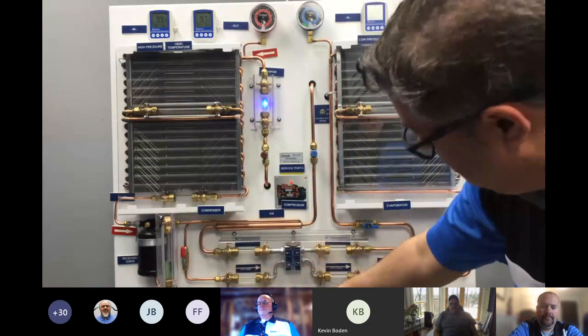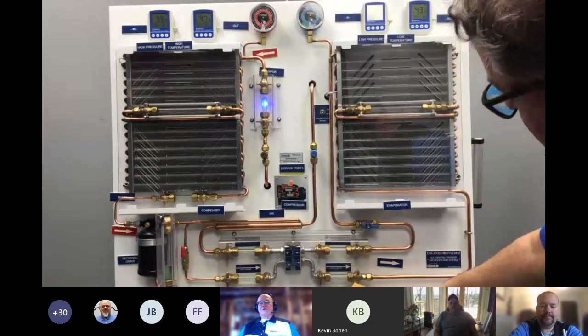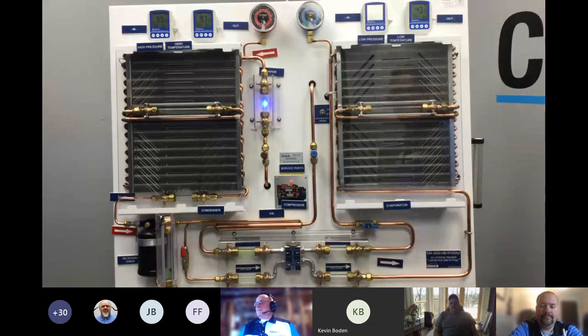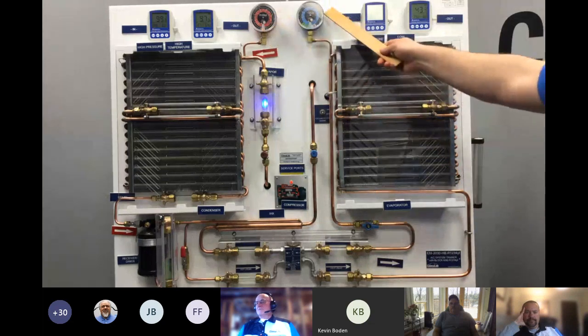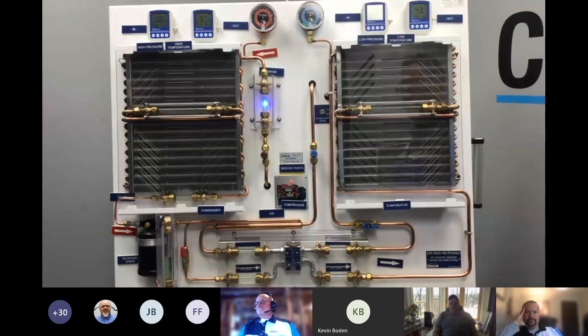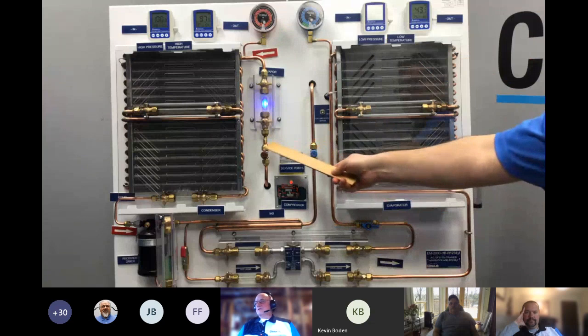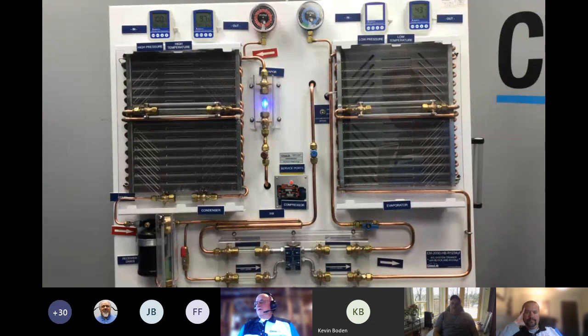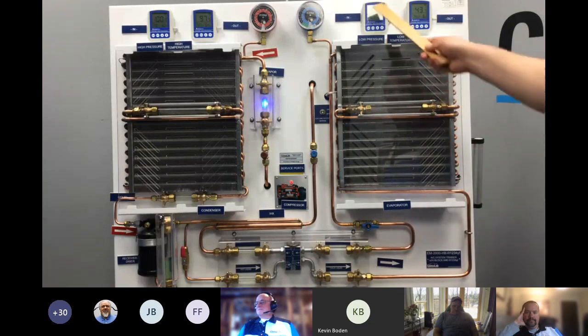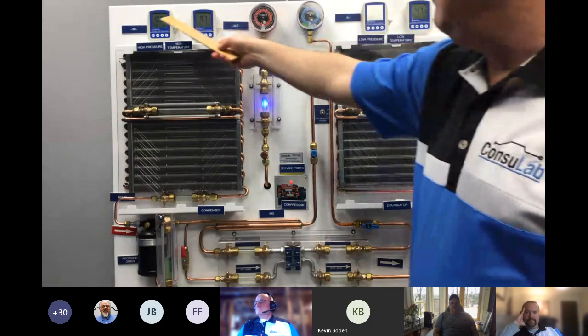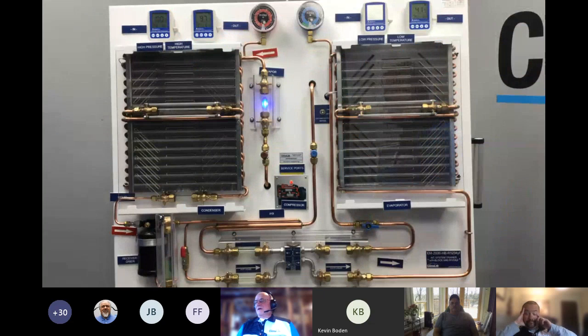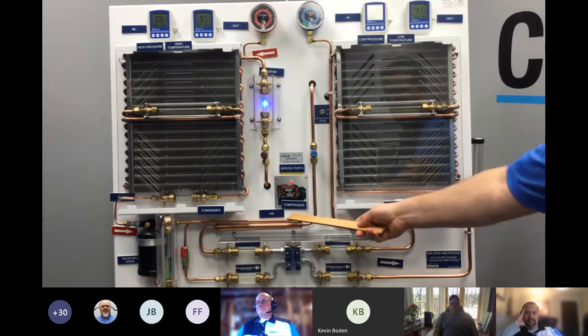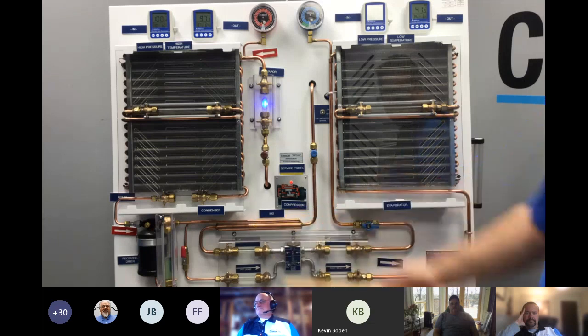That's a really neat feature. It gives visual learning of the change of state. High and low side pressure gauges, service fittings, hook up a recycling machine, inlet and outlet thermometers for the evaporator and the condenser, and the 2 items of concern today, the internal heat exchanger, or IHX, and the H block.